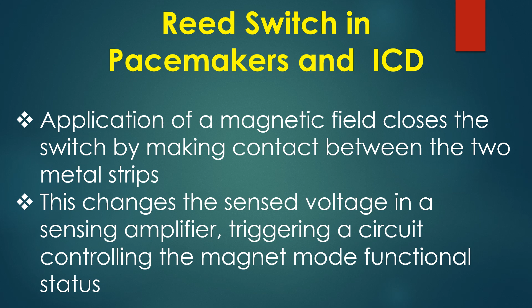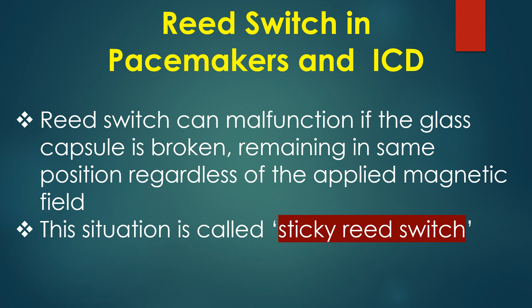Reed switch can malfunction if the glass capsule is broken, remaining in same position regardless of the applied magnetic field. This situation is called sticky reed switch. The exact effect of magnet application on the various functions of pacemakers and ICDs will depend on the make of the device and the programmed parameters. But in general, the effect on pacemaker is that it stops sensing and functions in an asynchronous pacing mode. In case of ICDs, magnet application suspends all anti-tachycardia therapies without affecting the pacing mode.